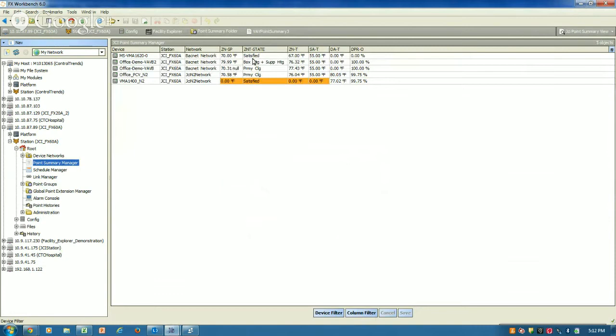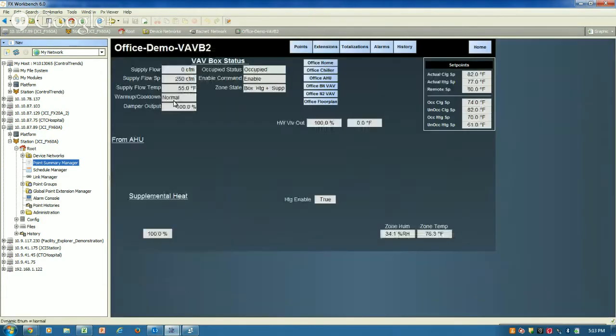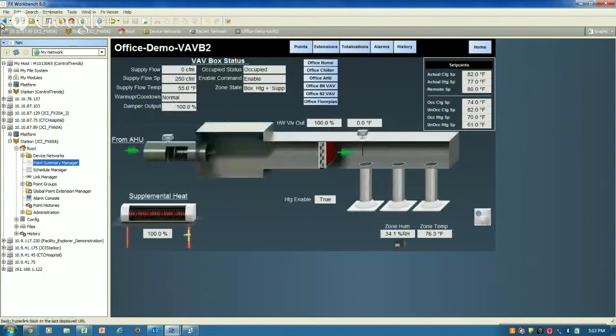It shows my set point, what state it's in, zone temperatures, supply temperatures, discharge, damper position, and whether anything's offline, overridden, or in alarm—shown in color, with normal status for all these things. Clicking on the particular name takes you directly to the graphic, and you can make these linkable to the home screen as well.